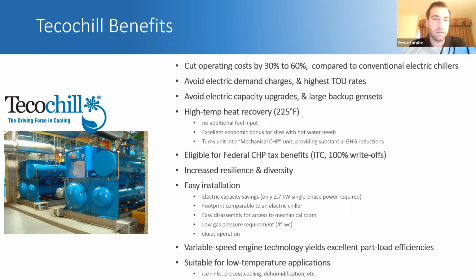And again, our heat recovery is really high grade heat. It's over 200 degrees. You can do a lot with it. You can reheat. We do pasteurization and process cooling applications. I mean, you can do anything with that heat. It's really high temperature. And again, it's a free byproduct. That's really kind of the most important thing is when you're comparing it to a heat recovery electric chiller, you're not incurring a compressor work penalty to get that heat.